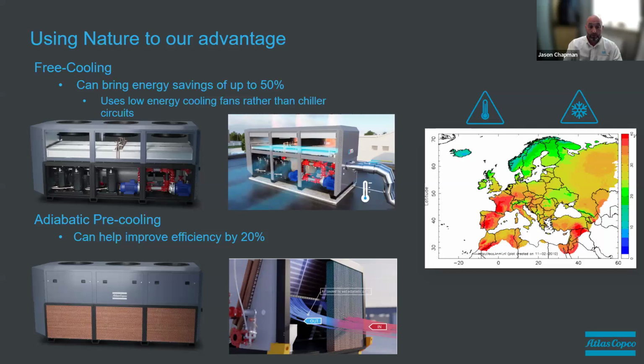So as you can see on the actual pictorial there, the warm air coming in, by the time it passes over the chiller pad, the adiabatic pads, has a reduction in temperature before it reaches the cooler, so they're not working as hard that way as well.